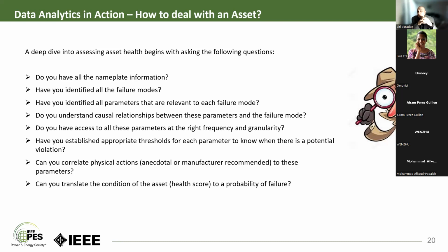Now the question becomes, if you understand the failure modes, do you know what parameters can be measured that are indicative of those failure modes? For example, if overheating is a problem, then obviously I'm going to measure the temperature. If the gas composition is a problem, then I'd put in a sensor that monitors the level of the dissolved gases, for example acetylene, and so on.